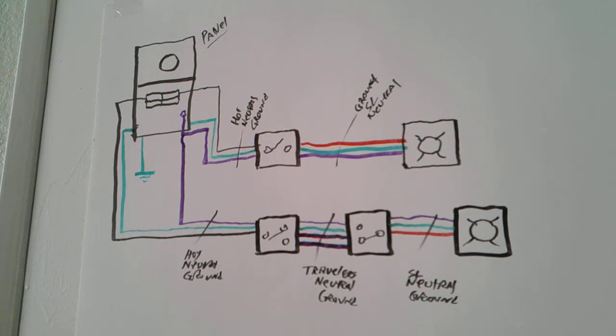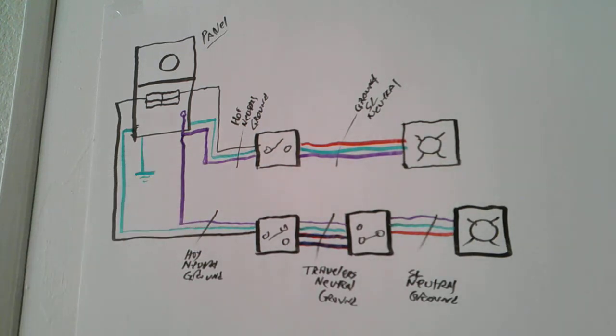Okay, so that basically tells you how to troubleshoot a circuit. Again, you start at your electrical panel and you go to your first group of wiring, because sometimes, when you're installing wire from the panel out to wherever you're going to install it to, whether it's a room or an office or something like that, sometimes you end up pinching wires or cutting wires or taking the insulation off. The bad thing is in residential, a lot of times what happens is the guys that hang drywall sometimes can run a drywall screw right through your wiring. And when that happens, you've got to open up the wall and fix that.